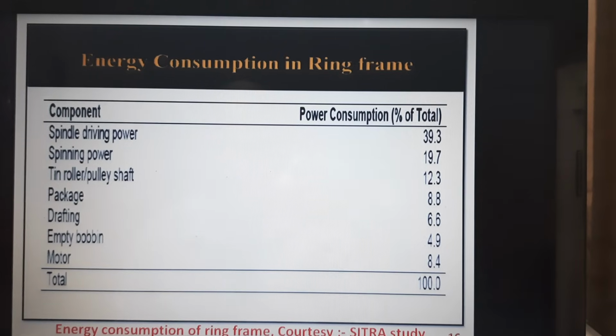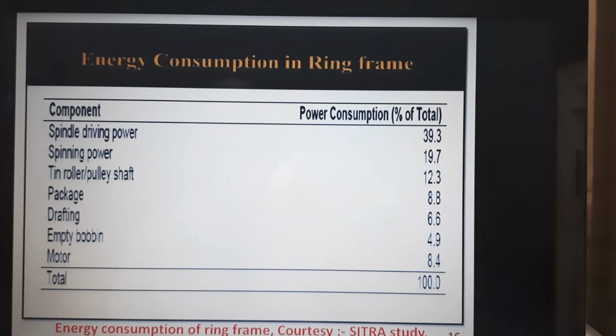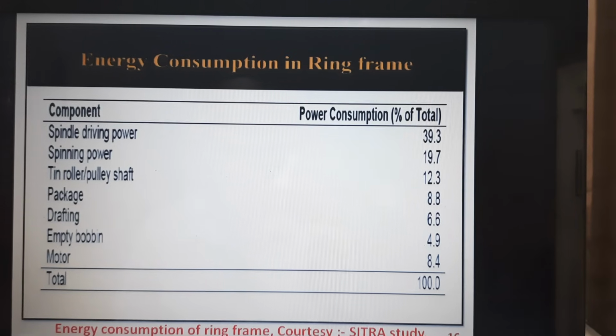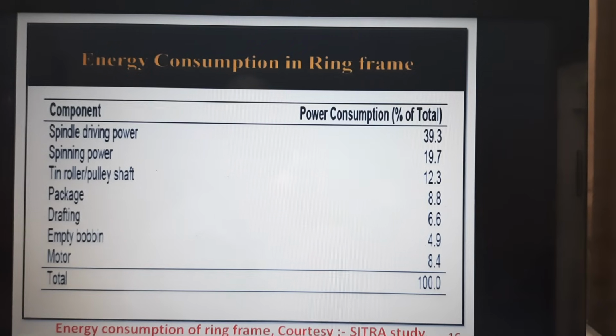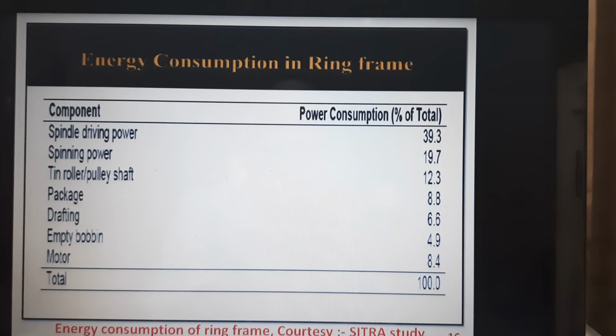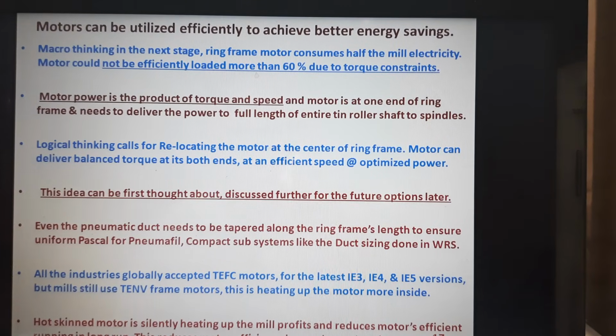SITRA always says the energy consumption of the ring frame is almost 20%. Thanks to SITRA for giving this real input, a practical statistic. Almost 20% energy is consumed. I don't say lost, it is consumed, between the tin roller shaft at around 12% and the motor at around 8%. This needs to be addressed, and wherever the self consumption losses are addressed, definitely this can be brought down from 12% to 6% and from 8% to 4% for the given motor. So overall, the 20% energy consumption norm can be brought down by half to 10% by reducing self consumption losses. So the motors can be efficiently utilized for better energy savings, provided they are operated at the right loading of around 60 to 80%.